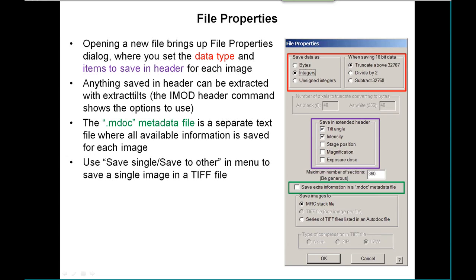When you go to open a new file, you come up to the file properties dialog, which gives you an opportunity to set the data type — usually either unsigned or signed integer — and also to set what items you want to save in the extended header. The extended header is a nonstandard component of the MRC file used for a number of years, but it's become a dead end because it was very difficult for others to get information out of it or to add more information. So there's a new method of saving information called the MDoc metadata file — a separate text file where all available information, not just the ones you ticked, can be saved for each image.